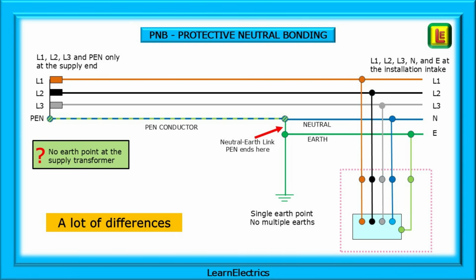Look at the conductor identification at the supply transformer on the left of the drawing, L1, L2, L3 and PEN. Now compare this to the identifications at the installation end on the right of the drawing, L1, L2, L3, neutral and earth, but no PEN conductor. From the three-phase intake position, we treat the installation as we would any other installation. We can install three-phase equipment, take single-phase feeds off it, install a single-phase consumer unit, and so on.